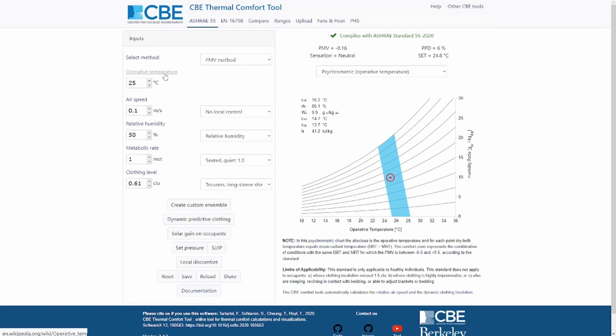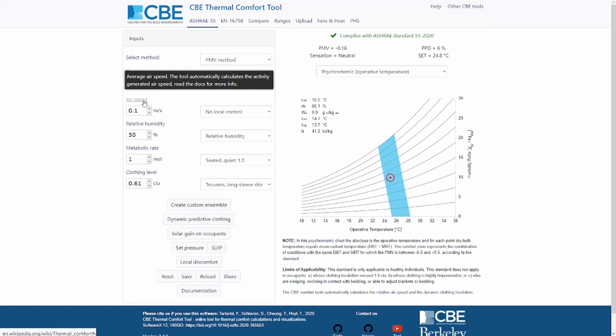It is very important to note that the airspeed that you enter in the model is actually the measured airspeed. ASHRAE 55 recommends that you measure the airspeed at three different heights based on the body position of the participant. So if the person is sitting, you should measure the airspeed at 0.1, 0.6, and 1.1 meters and then average these three values.